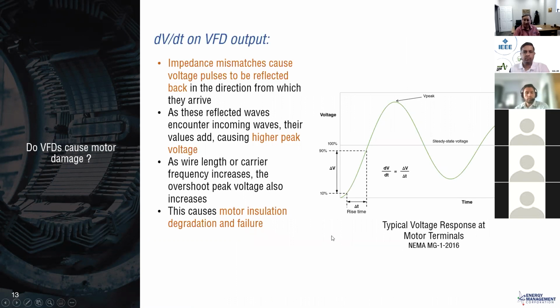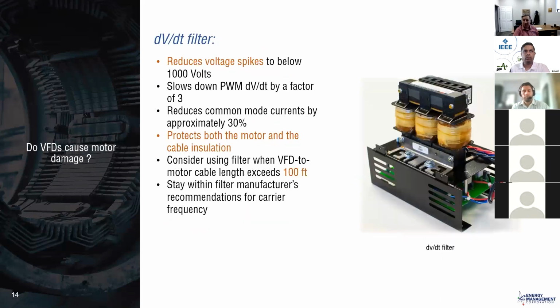Also part of NEMA MG1 is this rise time. The way they measure rise time is from a stable voltage of 10% to 90%. And they're looking for the slope of that to measure the rise time to be below that 0.1 microsecond. And of course, the peak voltage is this. Now you remember from that waveform, and I think I probably got another slide that might show this more. The reason this is happening is because of the reflected wave phenomena, that when you have an impedance mismatch, you're sending one of those PWM pulses down the conductor, and it's going to have capacitive coupling. It's going to see inductances, and in certain situations, it's going to be doubled or even 4 times in a reflection back to the motor. I don't have a slide of a ringing wave, but I think everyone can kind of visualize this pulse that you're sending down a transmission line, and it's bouncing back at you at a higher than initial rate.